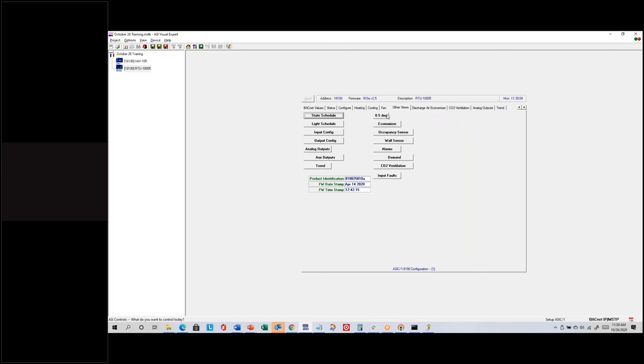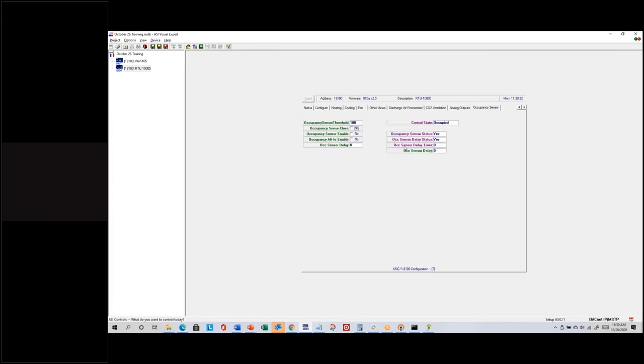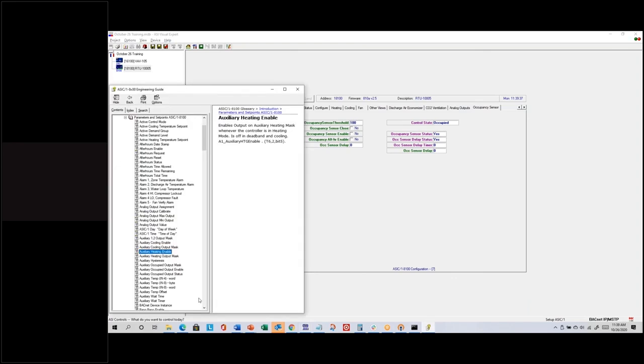There are half-degree settings in the ASC1s we don't usually use. In Fahrenheit cases they're intended more for Celsius customers, since one degree Celsius is almost two degrees Fahrenheit — sometimes they want to set set points in half-degree increments. I don't recommend it for Fahrenheit cases; it's usually not needed. Occupancy sensor is not commonly used, but you can connect one — the wiring diagram shows it on input 8.